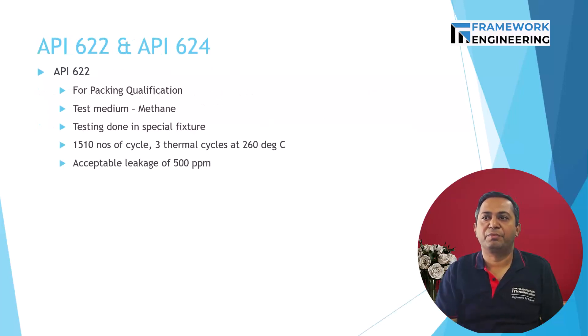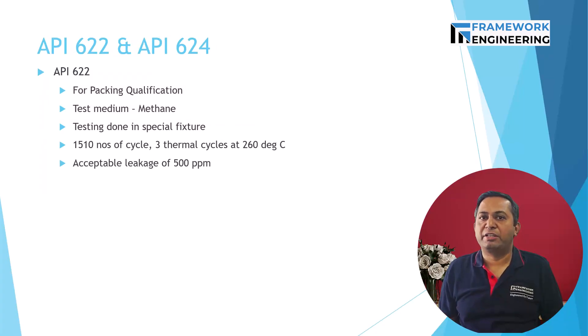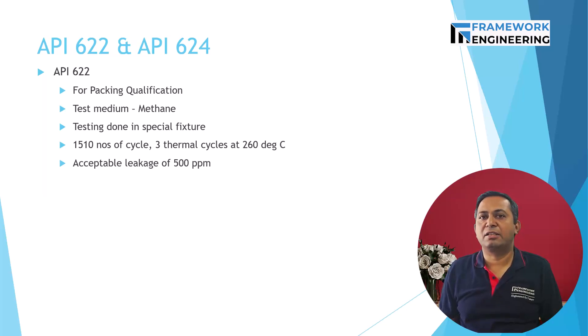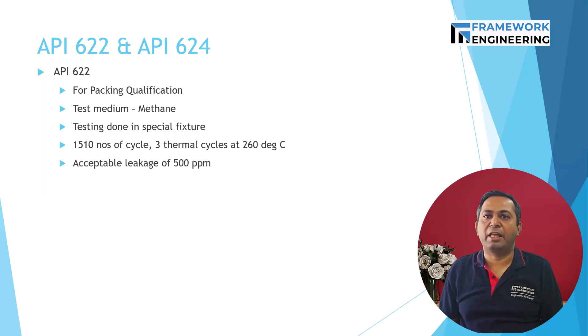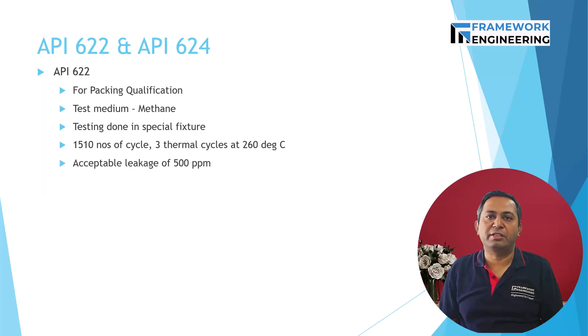The next standards are API 622 and API 624. API 622 refers only to packing qualification. The test media is methane and testing is done in a special fixture — not on a valve itself. 1510 cycles are performed along with 3 thermal cycles at 260 degrees centigrade, with an acceptable leakage of 500 PPM with no packing adjustment.